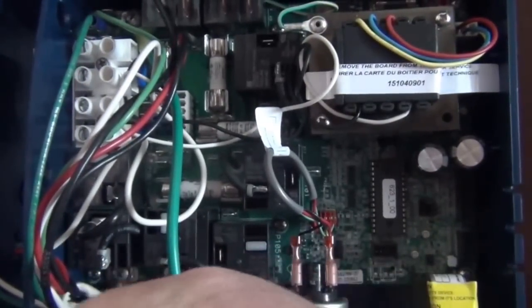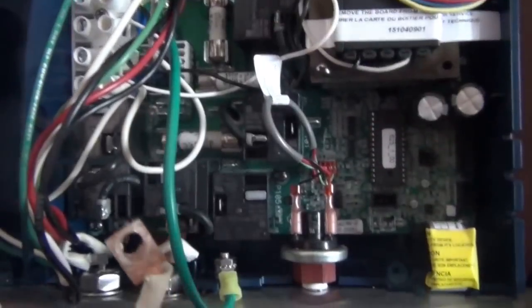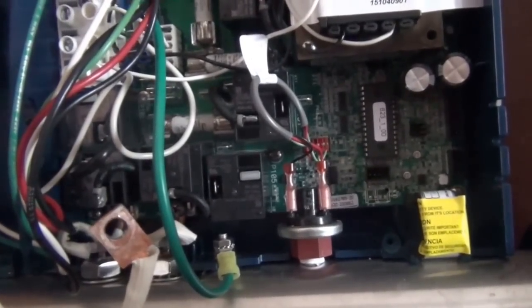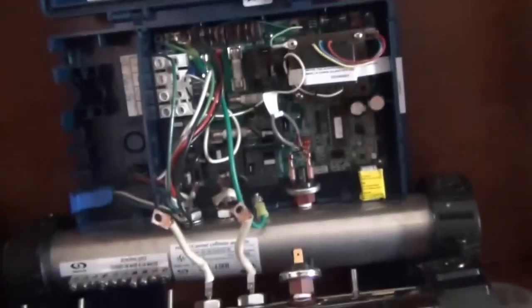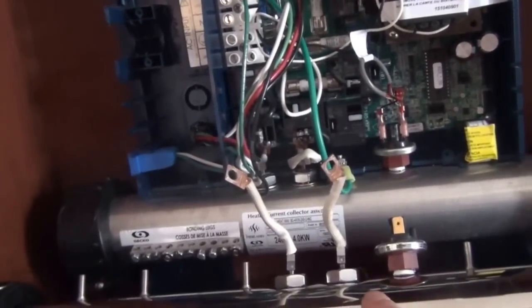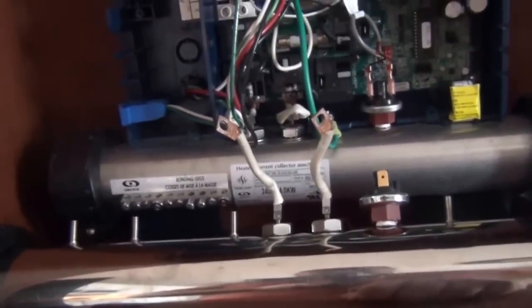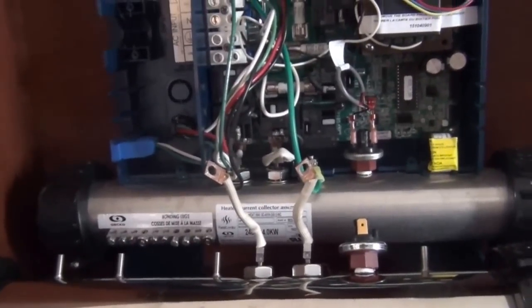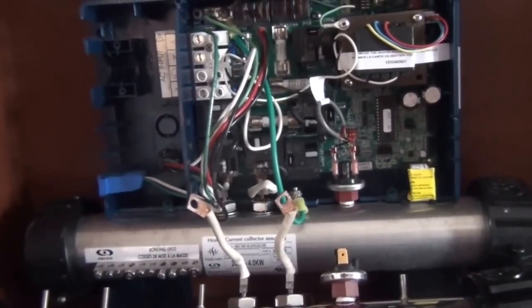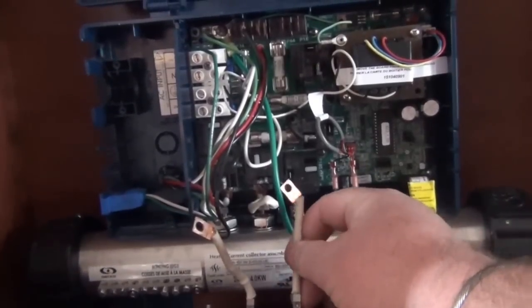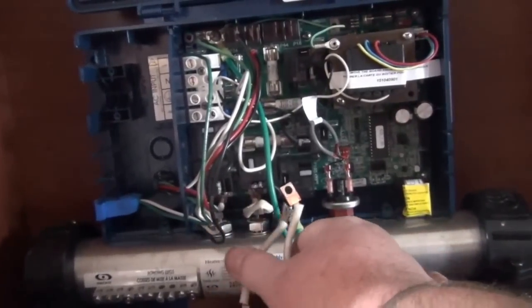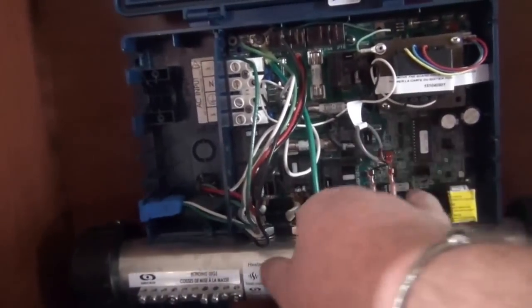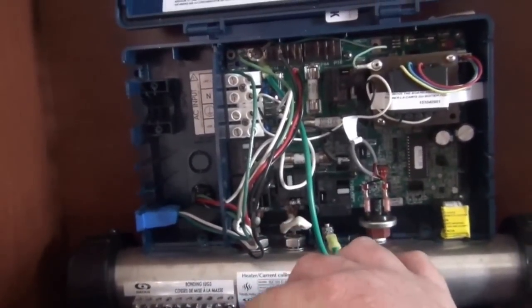Pull these wires back, make sure you're not touching anything, turn GFI back on. Now if the GFI stays on, it's your heating element inside. So you gotta replace this heating element. I'll do another video on how to replace an element, this style or even one with the bolts. Same idea.